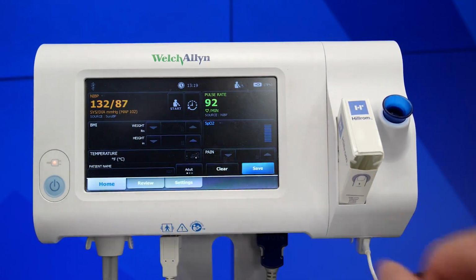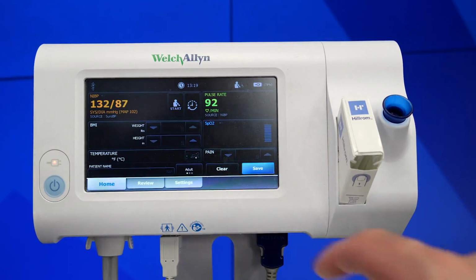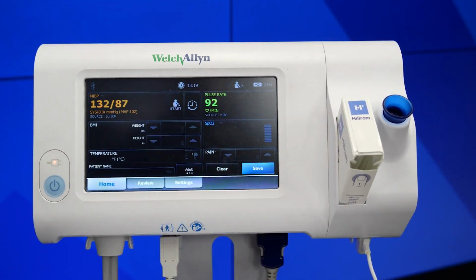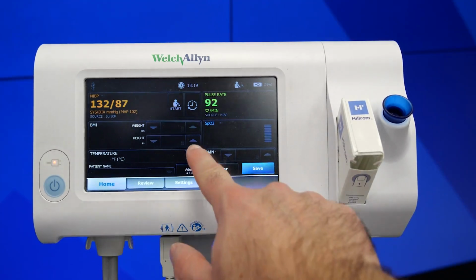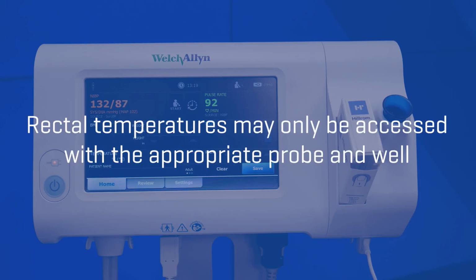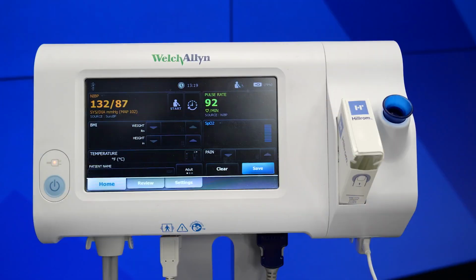When pressed, it will change between oral, pediatric axillary for ages 17 and under, and adult axillary mode. Please note that rectal mode can only be accessed if the appropriate probe and probe well are attached to the monitor. Once connected, the rectal icon will appear automatically. To distinguish between oral and axillary thermometers, refer to the color. Blue is for oral and axillary measurement.